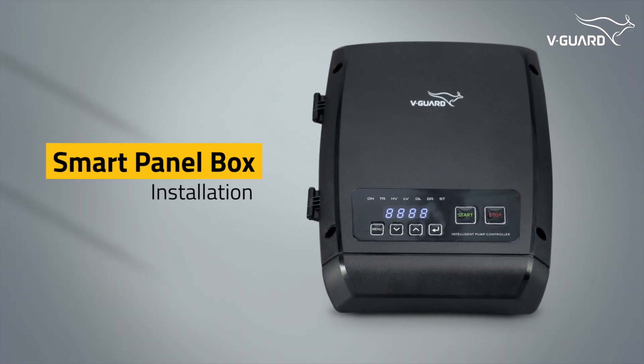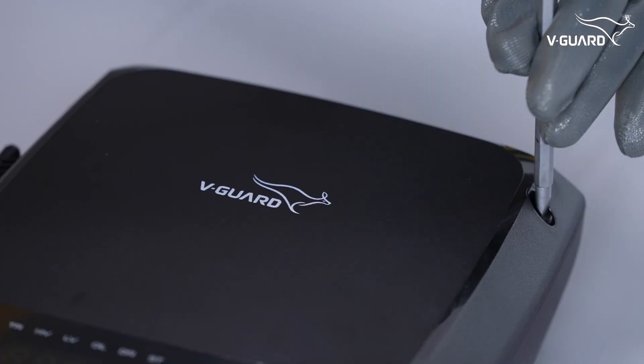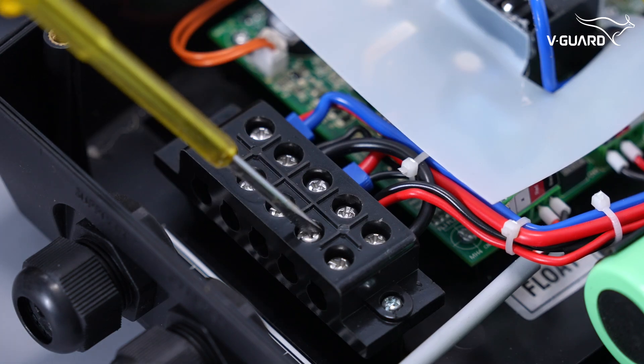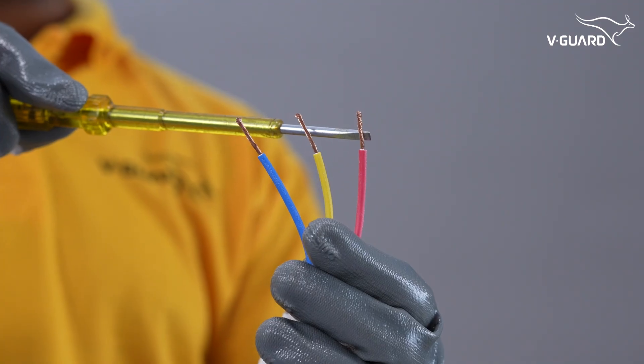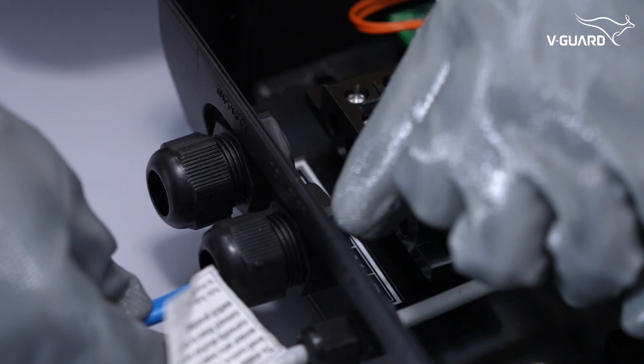Let us now see how to install the V-Guard AquaSmart Borewell Submersible Pump. Unscrew and open the intelligent pump controller. Follow the wiring diagram provided in the user manual. These are the R, Y, B — or red, yellow, and blue — terminals. Connect the R, Y, B cables from the motor to the corresponding terminals in the intelligent pump controller.